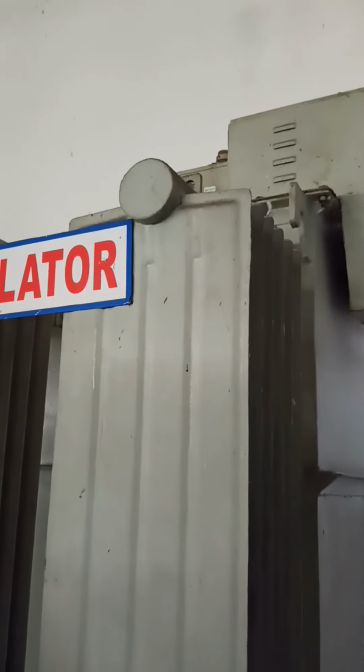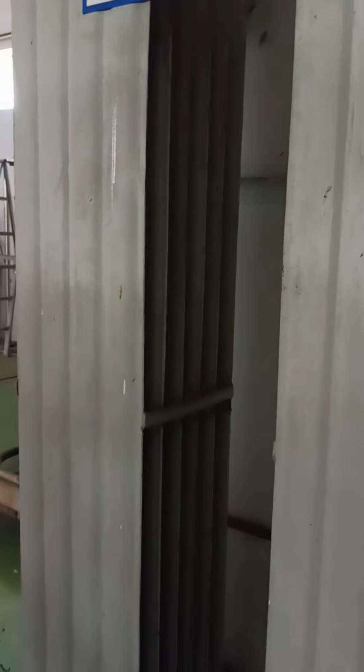The primary thing in a transformer is voltage step up and step down. But the other instruments you will get are one for cooling and the other for insulation. For insulation we are using oil. With rising temperature, the breakdown voltage of oil also decreases. So we need to control the temperature of the oil so that it works in its normal or safe zone. For that we need this cooling provision.